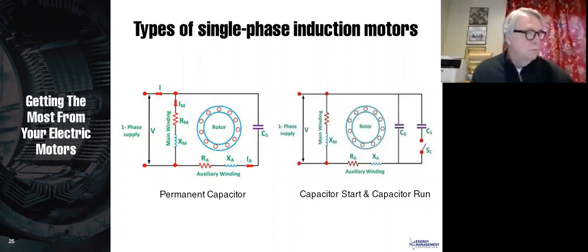Great. How is the power factor of the motor decided in manufacturing? Is it recommended to put additional capacitors to increase the power factor? Yeah, that's a really great question. So the power factor of a motor goes into this big mix. When you design a motor, you want to design a motor that is reasonably low cost to build, because if you have higher costs, then you're going to lose jobs due to cost. You want a motor that is going to be as efficient as possible, because a lot of people look at efficiency, and we also have standards for efficiency.